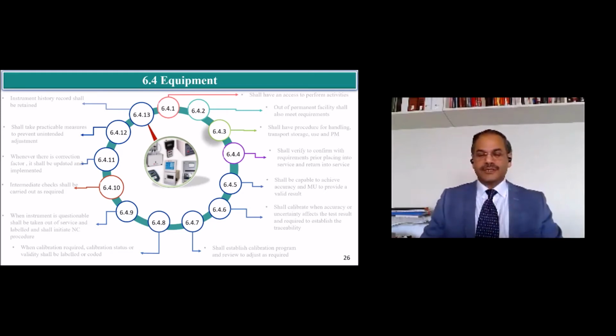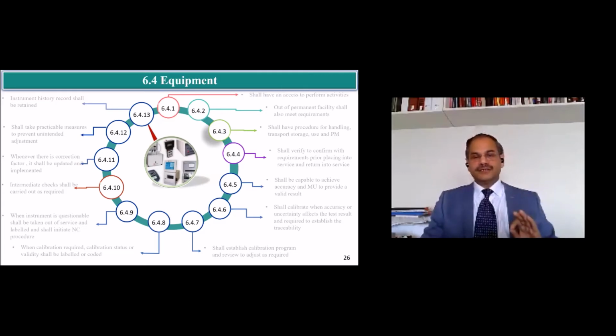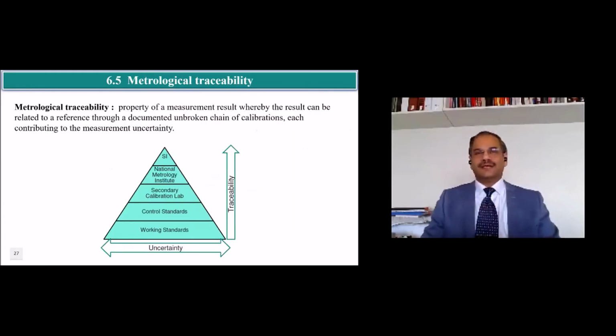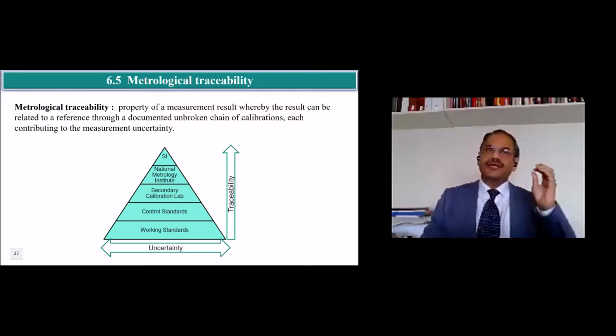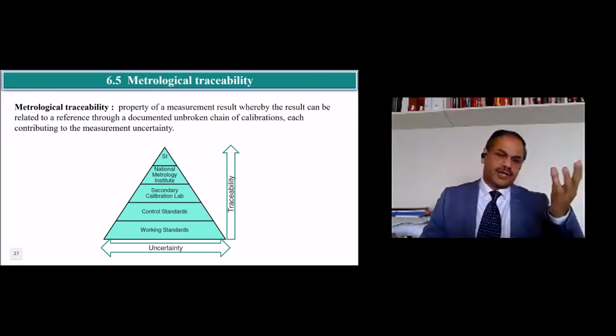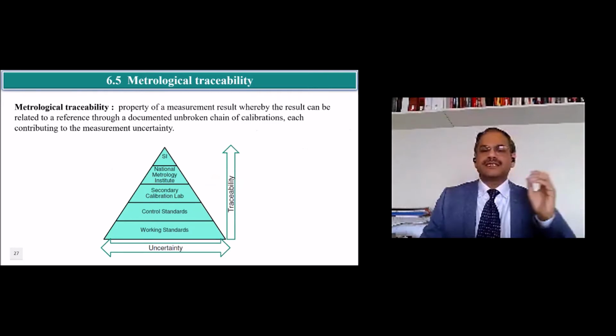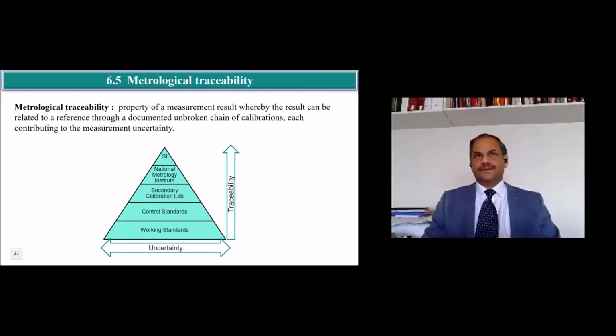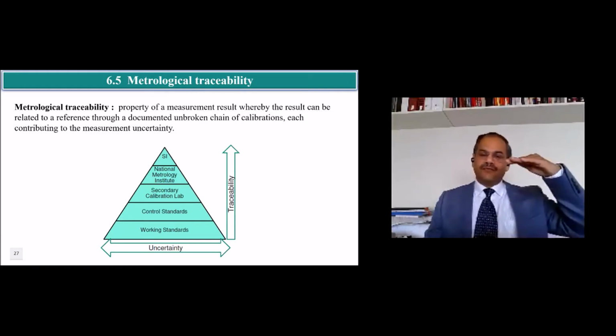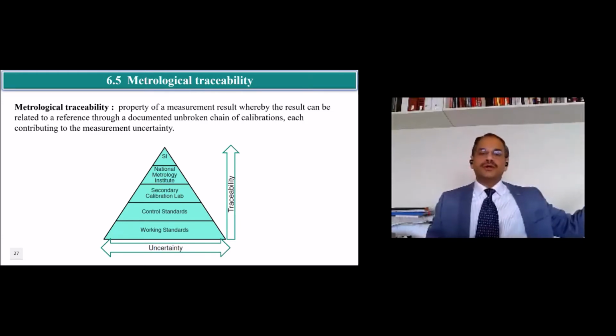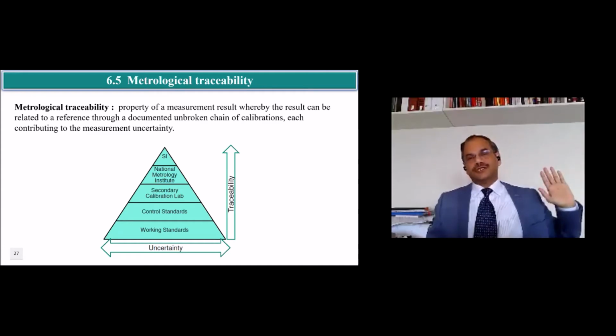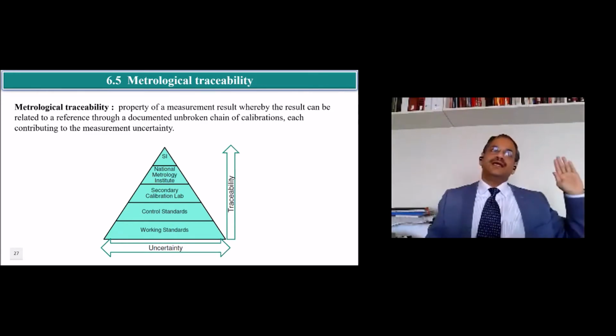That's a very good question, and most of the things are coming. Now, when I have the calibration, 6.5 is talking about metrological traceability. How should it be maintained and why? Because you have your own lab, and that has to be connected in some way to the SI unit or a National Metrological Institute, an NMI. In our case, I think it is NPL India or NPL UK, or NIST. Whatever the traceability is, it has to be connected to the SI unit. It has to be taken care of by someone who has a standard traceable to NIST, or to the National Metrological Institute in your country, or any international lab which directly has traceability to the SI.